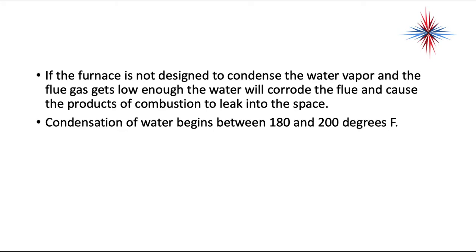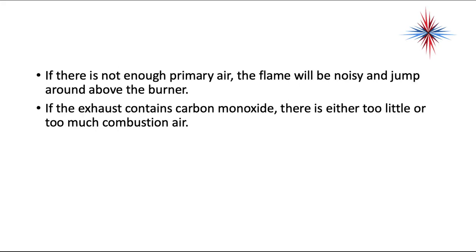Condensation of water begins between 180 and 200 degrees Fahrenheit. If there is not enough primary air, the flame will be noisy and jump around above the burner. If the exhaust contains carbon monoxide, there is either too little or too much combustion air — you do not want carbon monoxide.